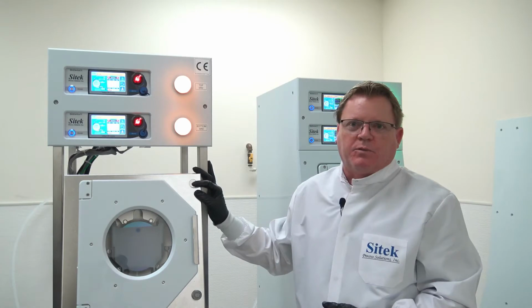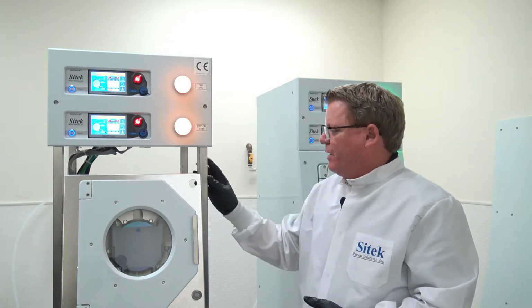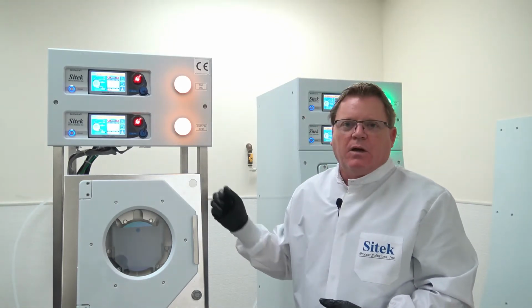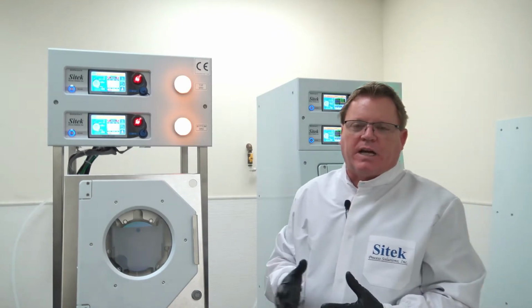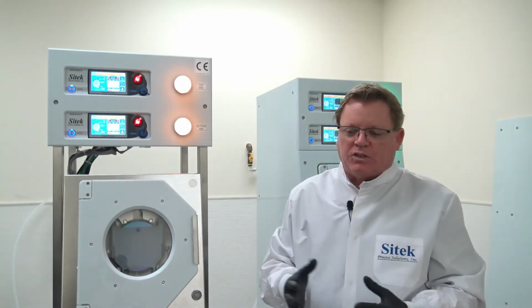Then we hook the DI water up to it without any of the outer skins or frames. We make sure all of the lines are tight, all the ACR valves hold, everything's good. We go through approximately 50 process runs.